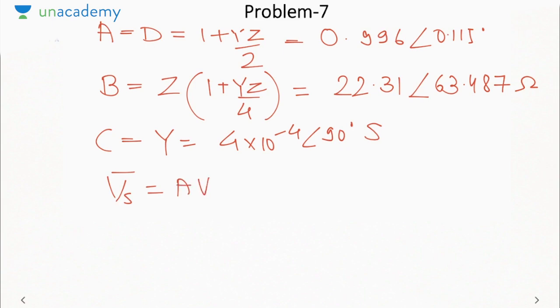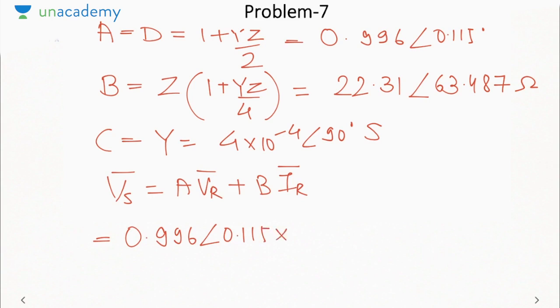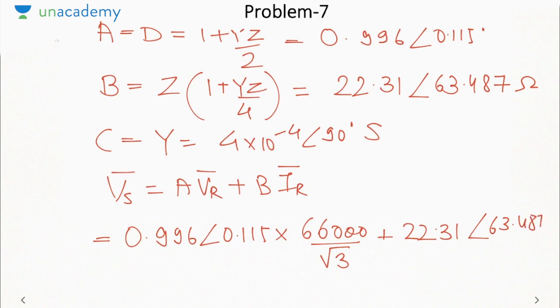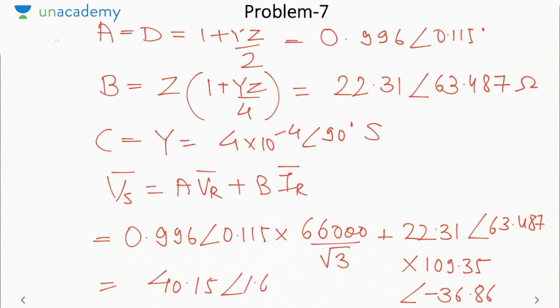Now we need to find Vs. Vs is A VR plus B IR. That is 0.996 angle 0.115 into 66,000 by root 3, plus 22.31 angle 63.487 into IR. IR will be how much? 109.35, and the power factor was 0.8, so angle minus 36.86. So this Vs per phase will come out to be 40.15 angle 1.67 degree kV. But remember, this is a phase voltage because ABCD parameters are applied on per phase basis.